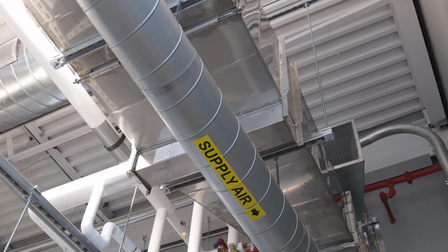You have to consider at that point that the air is going everywhere, which means the moisture is going everywhere. And so how do I determine whether I've got enough or too much? So you have to understand, okay, what's my control point? Is it in one room or am I aggregating that across the entire building? If you have a space where you're trying to control just a specific one, where I only need this space at a specific condition, you've got to get into individual control.